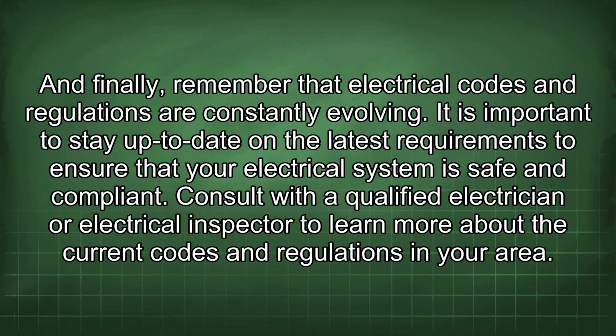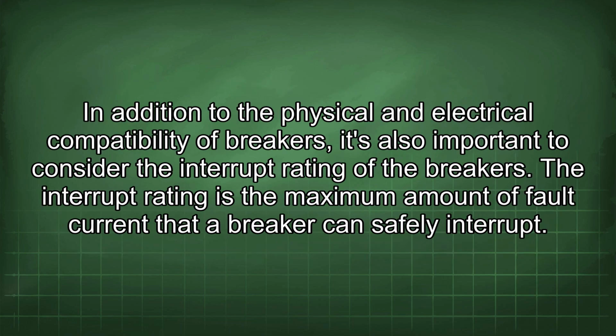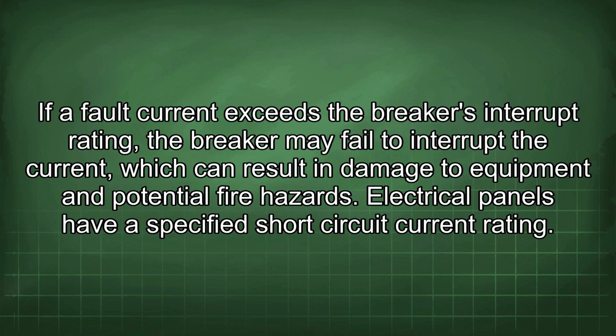In addition to the physical and electrical compatibility of breakers, it's also important to consider the interrupt rating of the breakers. The interrupt rating is the maximum amount of fault current that a breaker can safely interrupt. If a fault current exceeds the breaker's interrupt rating, the breaker may fail to interrupt the current, which can result in damage to equipment and potential fire hazards.